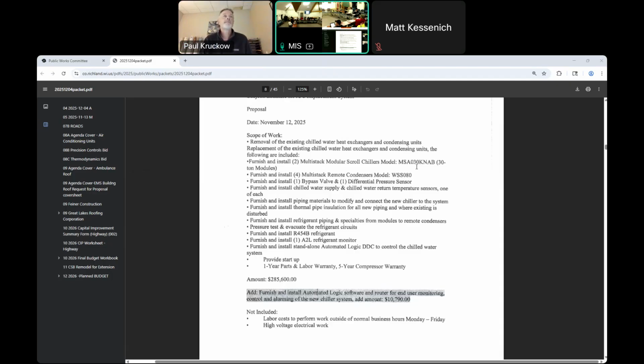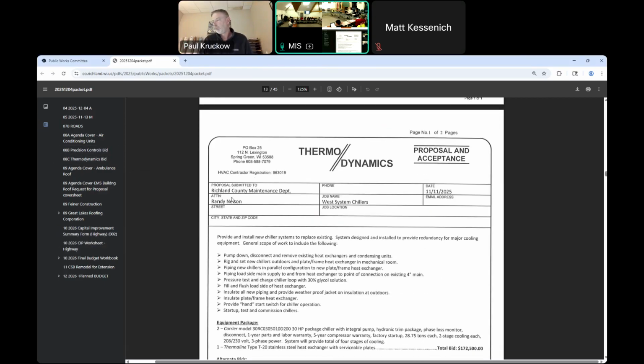All right. Well, let's look at the other bid so we can have some explanation on that one. Sure. So we took a little different approach to the project. Basically, our proposal is 2 packaged 30-ton outdoor Carrier chillers, and we would have a wet loop from those chillers to a plate exchanger mounted in the basement. Both chillers would have a pump on them. Both chillers have redundancy insofar as the compressors, which are 2 in each. So if a compressor happens to lock out, you still have a compressor on each one. 2 chillers gives us redundancy.